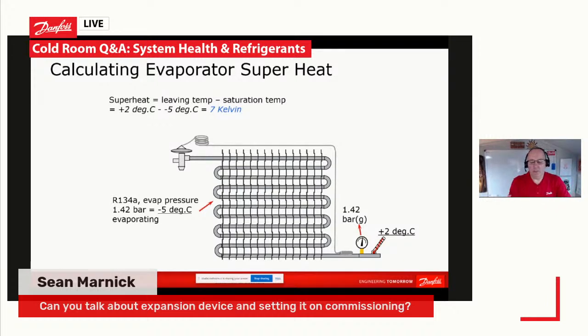Basically, an expansion device comes with, and I don't like to use this word, a presetting for the superheat. And on commissioning, you need to set up your superheat in your evaporator. The way that you do this, hopefully on the screen we can see that nice slide of your evaporator, and we've got our expansion device. Hopefully you guys can see my mouse. I think you can. So we've got our expansion device, we've got our evaporator.